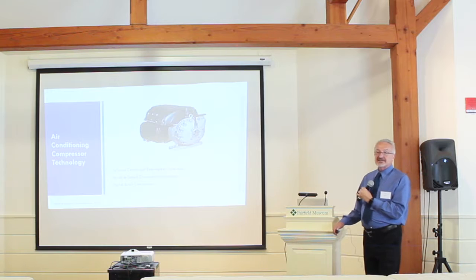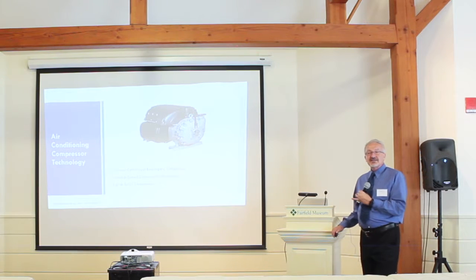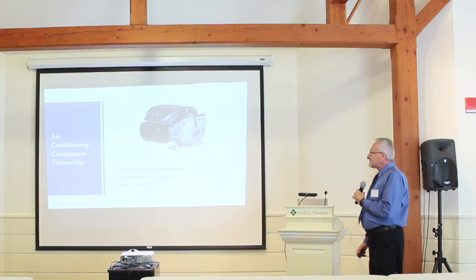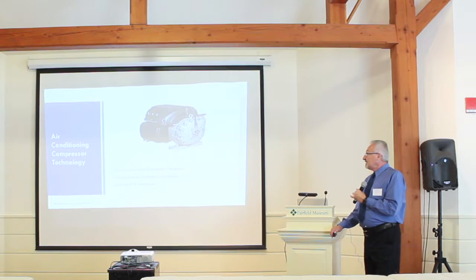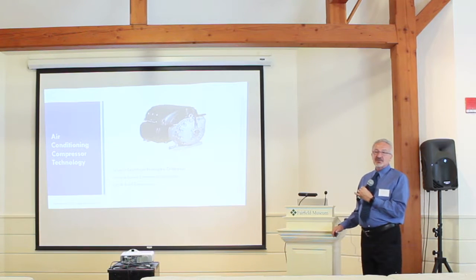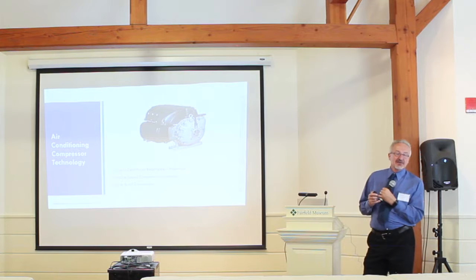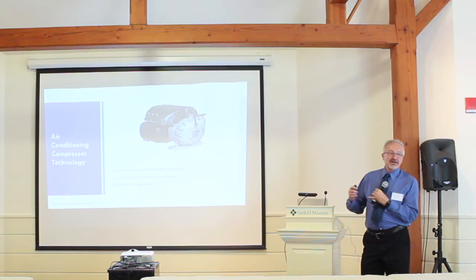Different types of HVAC technologies. Air conditioning units haven't changed all that much. The refrigerants have changed, to reduce global warming and to have less effect on the atmosphere or the ozone layer. But in regards to compressor technology, there are bearingless compressors, variable speed compressors, and digital scroll compressors, which make it as efficient as possible, but then match the load. Instead of having a machine just banging on and off, they actually vary the load. The compressor can infinitely vary to the load.